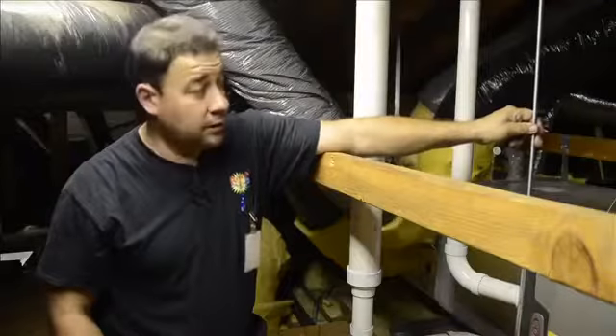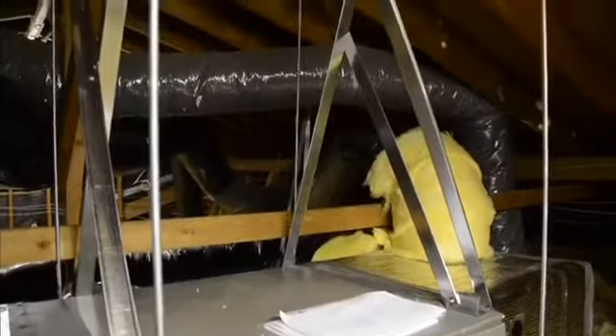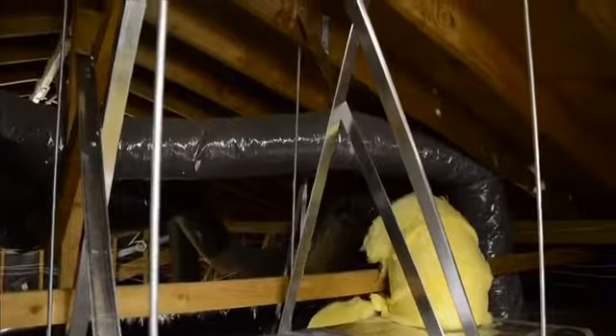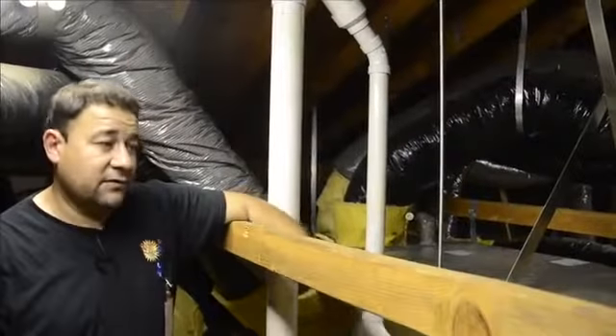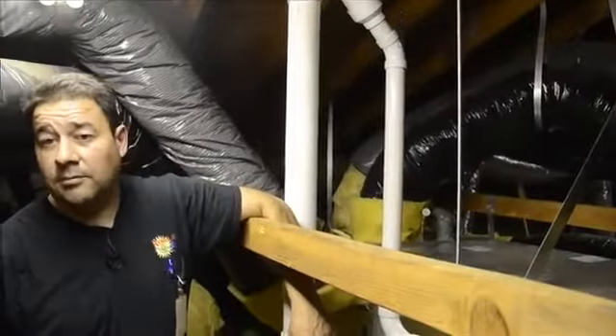We use the horizontal furnace installation hardware here and some cross bracing. The cross bracing is a little bit of overkill. It's not doing any support, but it supports it in an earthquake. Venting or gas flex line will not be harmed. In this installation, we utilized the existing ductwork. There was nothing wrong with the homeowner's ductwork.